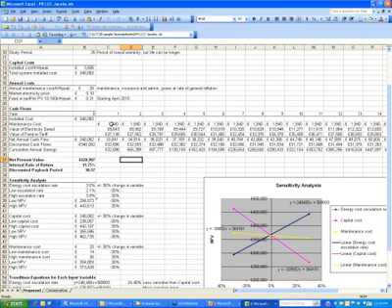This one does have full discounting. Maintenance, as you can see, is constant. Since it's in real rates here, we're not having inflation in that number. And then electricity, that's going up by the escalation of electricity costs. And you can do something, it's a bit tricky to do discounted payback period, but you have to pretty much sum everything up here, and then when you get to the year where you eclipse your capital cost, do a linear interpolation. I'm sure there is some software that can do it a bit more elegantly.